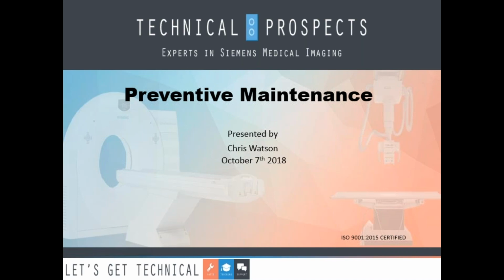The governing bodies like the FDA and JCAHO, they're going to look at all your service records, but they're going to scrutinize preventive maintenance the most. They expect to see issues, and when they don't, they think something's wrong. Now, granted, not every PM had issues, but if I had even a slight issue, I'm noting it. That way, when they came in and inspected what I was doing, I would say something like, okay, step whatever failed, performed such and such, recalibrated the system. They'll look at it and go, okay, at least you did something.